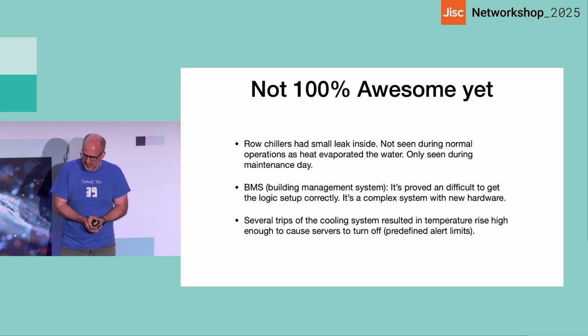As I said, the old data center declined quite quickly over 15 years. We don't want that to happen again, because this room probably needs to work until 2040 at least. There is a concern about the leaks. We have water above us. If it leaks onto the servers, that's a big problem. We have leak detectors installed and a monitoring system with alarms. And it isn't the highest density system you can get now. Some modern data centers are talking about 40 kilowatts, 80 kilowatts. This is clearly not going to be for that sort of equipment. So it is within its scope. It's doing what it can. It's not 100% awesome yet.